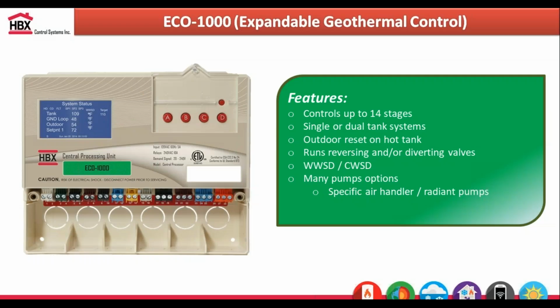Lastly, not going to get into this too much, but our geothermal controllers are really the same basis as our boiler controllers. Our Eco 1000 can do up to 14 heat pumps or chillers. So it doesn't necessarily have to just be used for heat pumps. It can also be used for chillers. We can do single or dual tank systems. Again, you can run your outdoor reset for your hot tank.